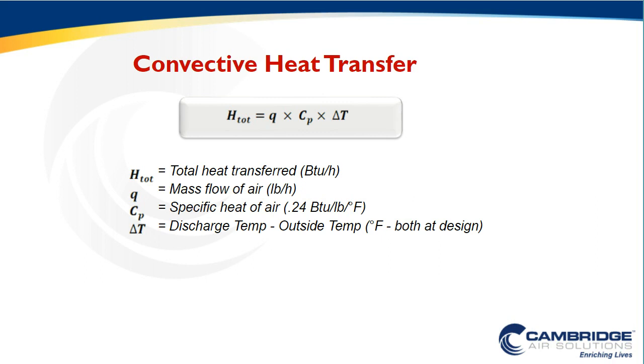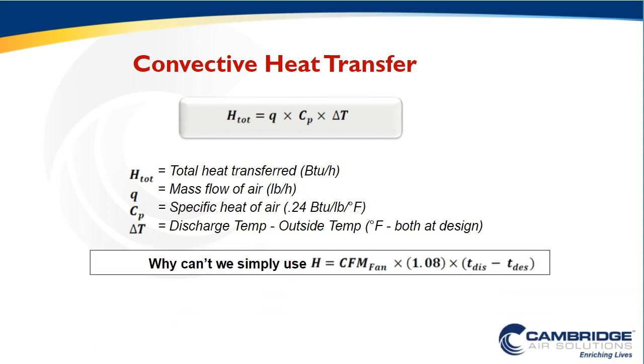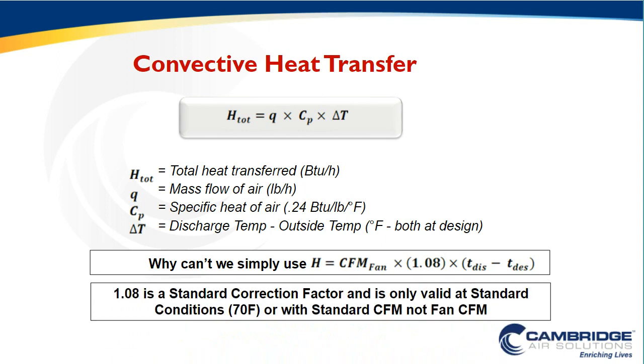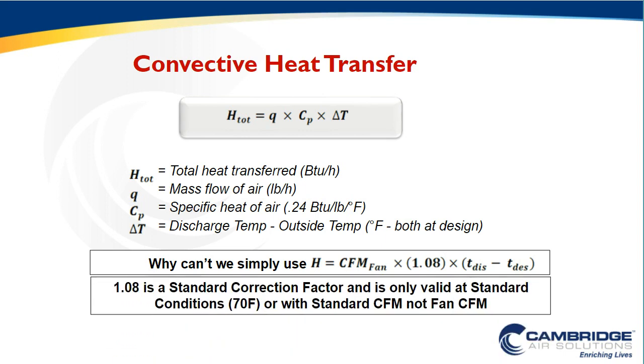And you may ask yourself, well, I use this simple equation every day, and it hasn't burned me yet. 1.08 times CFM times delta T. Well, there's one key assumption to that 1.08, which I'm sure many of you use, again, every day. And that key assumption is what we call standard air, right? 1.08 only works in one condition, 70 degrees and sea level. Now, I will argue that doesn't mean you have to go back in and reevaluate and redesign all of those mechanical systems you designed today, last week, or last year. But in most cases, in a lot of office spaces and recirculation systems, you're looking at it from 55 to 80 degrees. 1.08 might cover you.